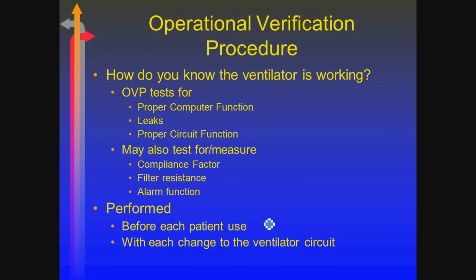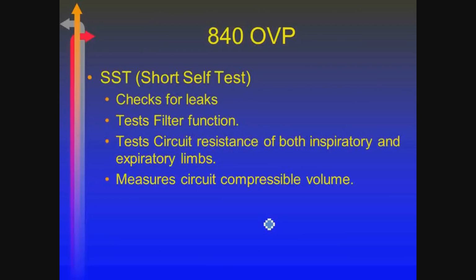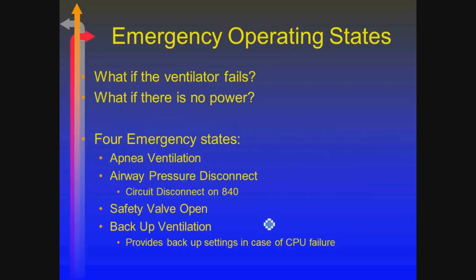Usually, like I said, it's done and stored. And if you do change the ventilator circuit, as I said, you need to recalculate the compliance factor in the process. On the 840, it's called SST, short self-test, and we'll walk through on each of the three how they're done. And then finally, there's some emergency operating states: what happens if the ventilator malfunctions?